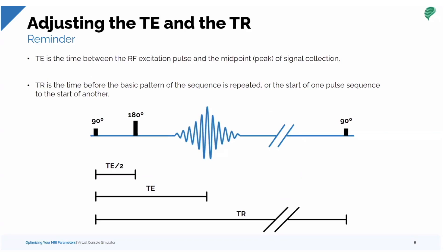Reviewing the parameters: TE is the time between the RF excitation pulse — the 90-degree pulse — and the midpoint of our echo, our signal that's received. You can see the TE from the 90-degree excitation pulse to the midpoint of the echo. The TR is the time between the start of the pulse sequence with the 90-degree excitation pulse all the way over to the start of the next pulse sequence. Things happen within that TR period, such as rephasing and refocusing.